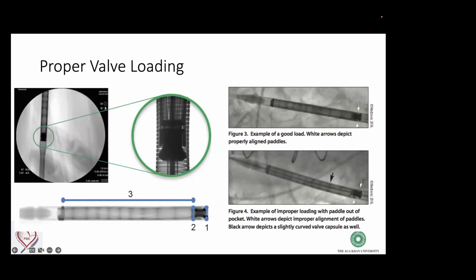If the paddles are off in any way, so for instance, in this, the paddles are not quite symmetric. Here you can see the paddles are equal and are right where they need to be. Here, one paddle is very close to the hook, and the other one there's a distance. This is not right. So you need to reload this valve. So take your time looking at these valves, make sure it's been prepped appropriately, and there is no asymmetry anywhere. It should all be very equal and symmetrical.